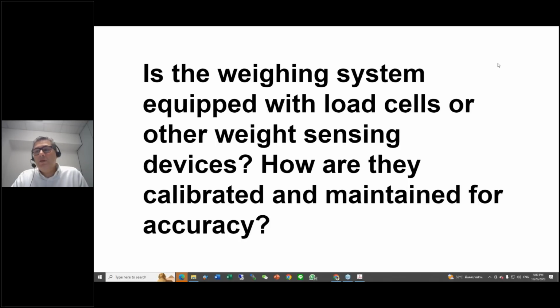That happens according to the customer's quality control, the quality check that has to be made according to the certification or as the customer requires. It can be made every day, or every 6 months, or every year. So the frequency depends on the internal regulation, I mean the customer regulation, but what we can offer is to help the customer identify how frequently the calibration makes sense, or, in case a trouble happens and I have to remake the calibration, how to understand when is the right moment to do it.